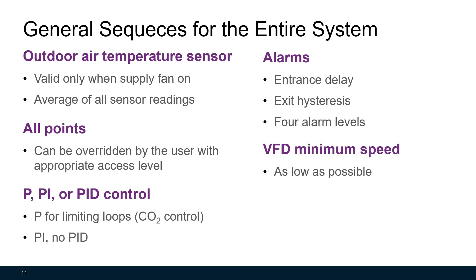In this guideline, there is a section describing general sequences applicable to all systems. For outdoor air temperature sensor readings, they are valid only when the supply fan is on, and we should use the average of all sensor readings. All points should be able to be overwritten by the user with appropriate access level, mostly for emergency, testing, or debugging purposes. For control loops, only proportional or proportional-integral controls are recommended. Proportional control is only recommended for controlling CO2 levels, and PID loop control is not recommended for HVAC system control.